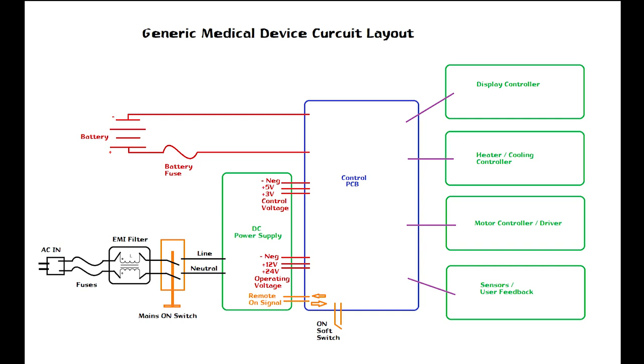And that, guys, that is 90-plus percent of medical equipment in a nutshell. This general little flow of how power comes in, goes to the control PCB, it maintains the battery, and it interacts with the various other parts of the device like your display controller, heating, motors, and your sensors.